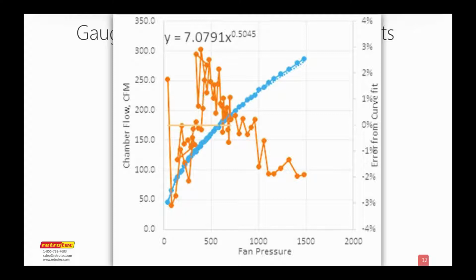You also made a comment about there being a 25% error on the duct blaster, and that's not the case. Most of them are fine. If they do have a problem, it is on ring 3, and most of them are within the factory tolerance, but we have measured them out as far as 25 and even 30% on that particular range. It seems ring 3 is the one that's problematic, perhaps because the ring itself is so close to the little tube where you pick up the pressure. So that would be the one that you should check, and you can check it quite easily by cutting a hole.